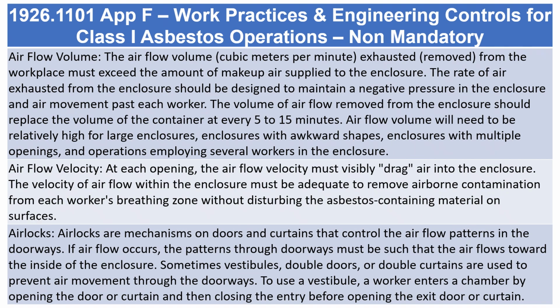Airflow volume. The airflow volume, in cubic meters per minute, exhausted from the workplace must exceed the amount of makeup air supplied to the enclosure. The rate of air exhausted from the enclosure should be designed to maintain a negative pressure in the enclosure and air movement past each worker. The volume of airflow removed from the enclosure should replace the volume of the container every 5 to 15 minutes. Airflow volume will need to be relatively high for large enclosures, enclosures with awkward shapes, enclosures with multiple openings, and operations employing several workers in the enclosure.